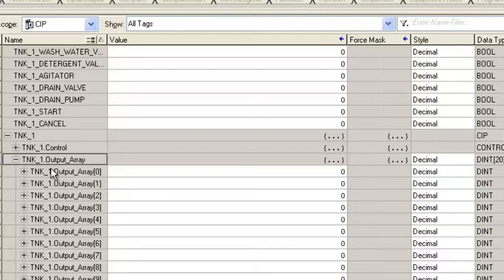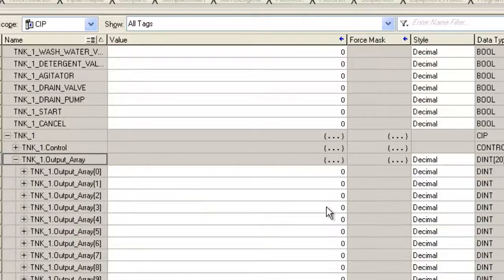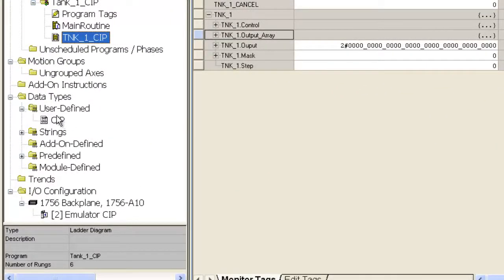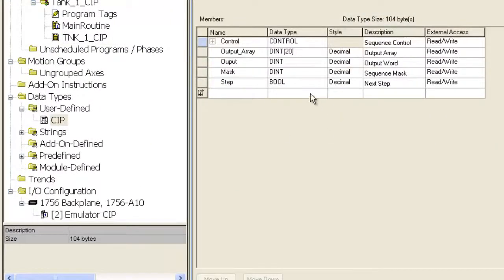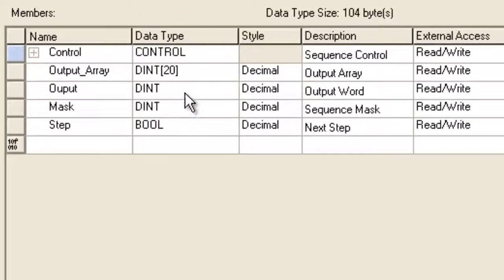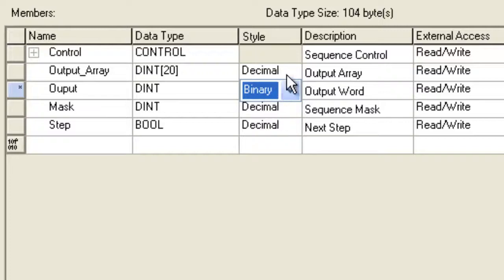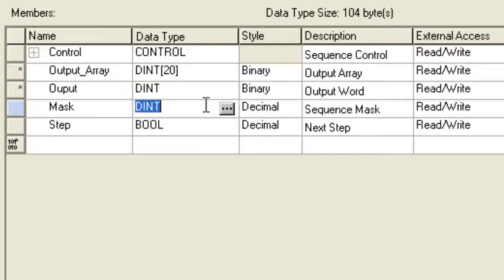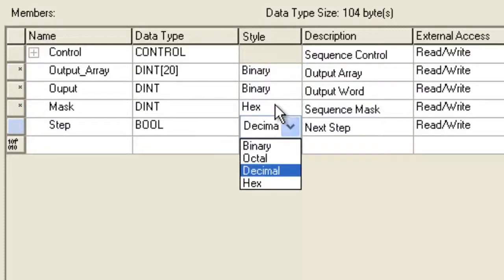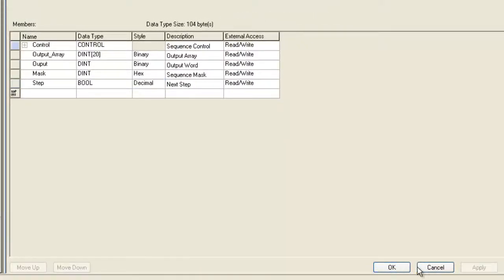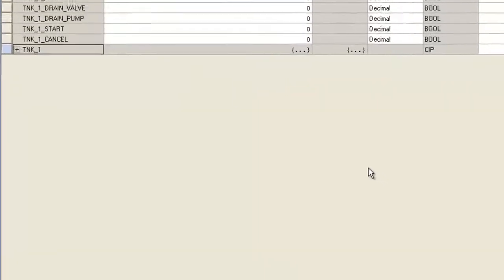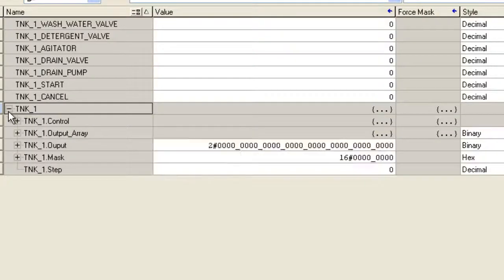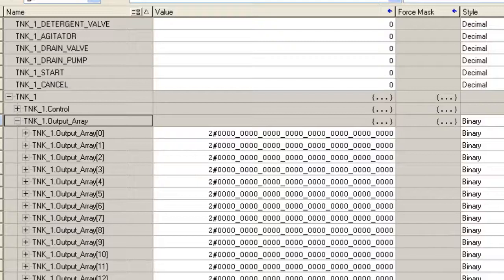I want to see that because we're using this at a bit level. I can go ahead and do this when I monitor the tags or if I just want it to be that way normally, I can come back into my control and change the style from decimal to whatever I want. I'm going to change it to binary on my output, binary on my output array, and on my mask I'm going to go ahead and put that as hexadecimal, that way I don't have to type in all the ones and zeros for my filter. Hit apply. Now we'll go back over here and monitor our tags and you can see that they're being displayed in the right style or radix.